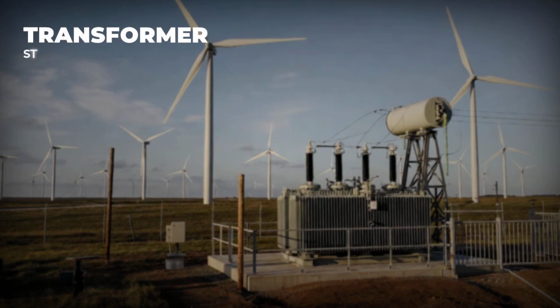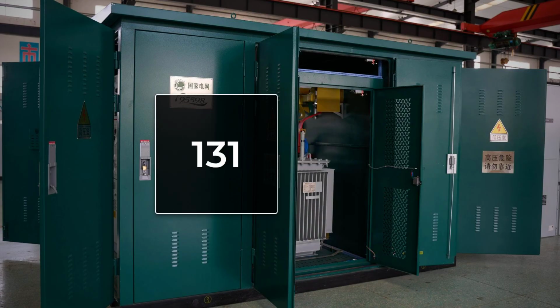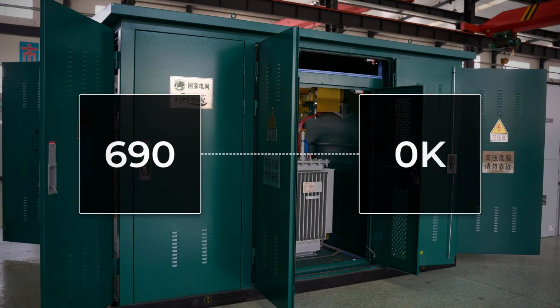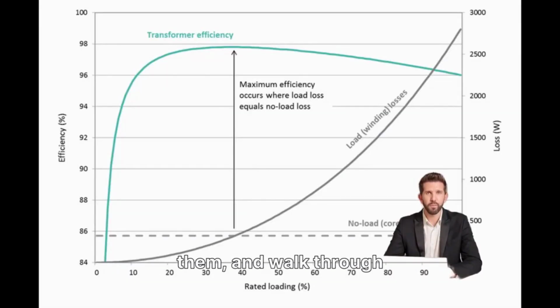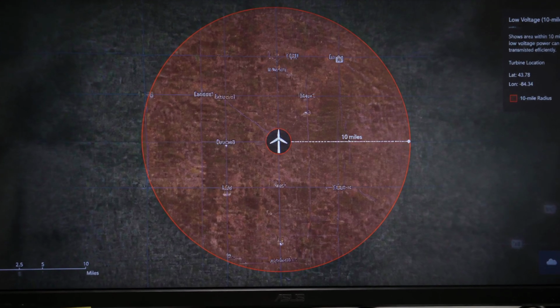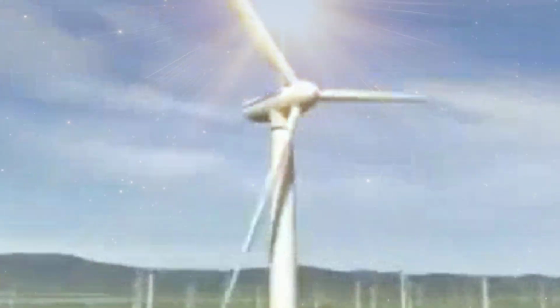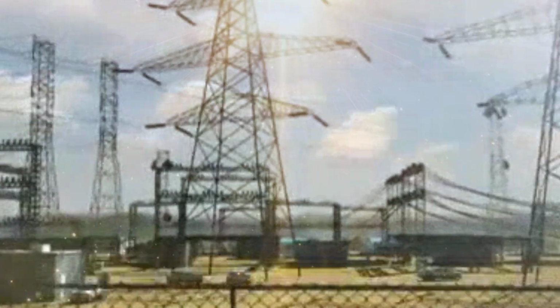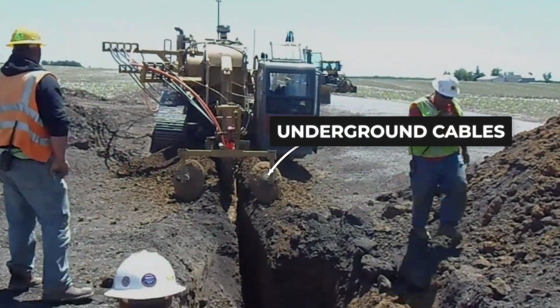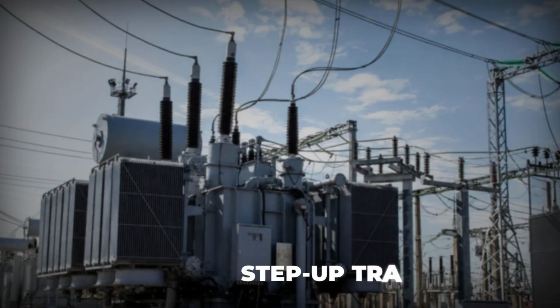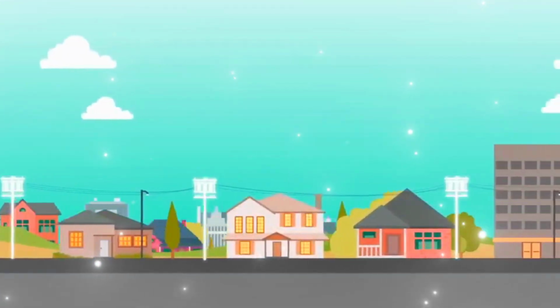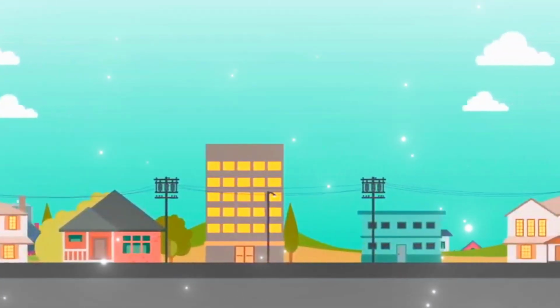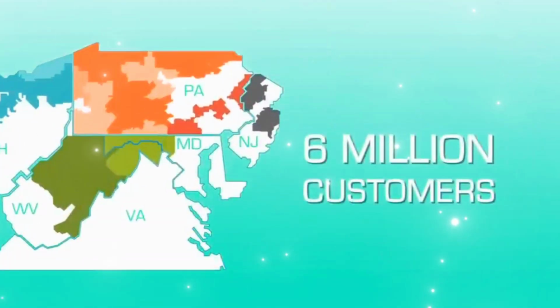At the base of the tower, the transformer intercepts it. The transformer steps 690 volts up to 33,000 or more, and in doing so, it trades high current for high voltage. Less current means less heat. Less heat means less loss. The electricity that couldn't travel 10 miles at 690 volts can now cross an entire region at 33,000. It flows from the tower base into underground cables, reaches a substation where voltage climbs even higher, and finally enters the overhead transmission lines that feed the grid, reaching homes and cities.